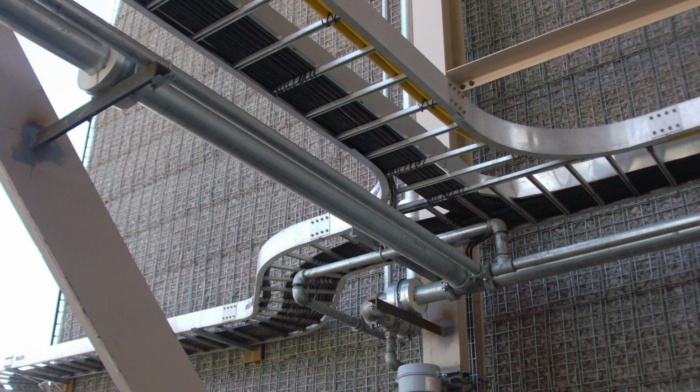It's very practical. So we're going to have to model these in Revit because it's something that people have to avoid. Like, you don't want to run a cable tray through ductwork. You also want to make sure you have clearances above a cable tray so that people can put the stuff into it. And you also need to make sure that you have room to put the cover on if it's running under an exterior ductwork.